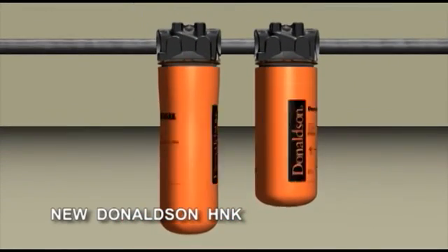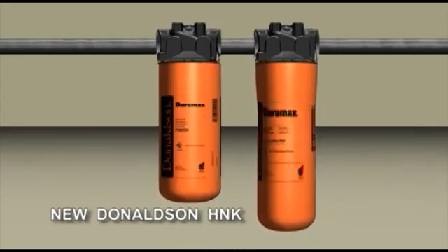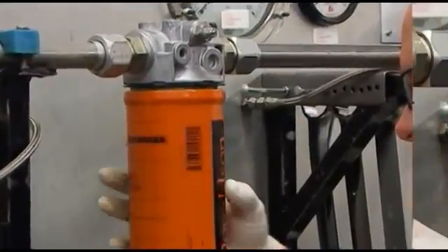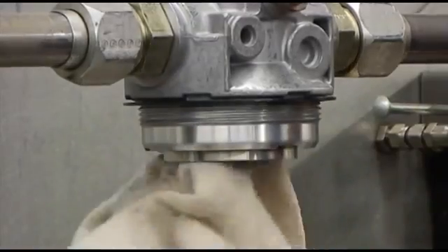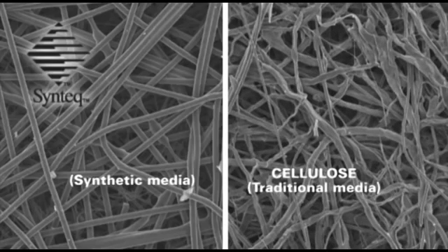This new Duramax filter allows you to choose between a spin-on or bowl cartridge style filter without changing heads. The new filter interface makes service easier and provides reliable sealing without having to torque to specification. Its improved performance is a necessity in some applications for meeting ever-increasing system cleanliness requirements. Although cellulose media will suit some applications, others may require Synteq synthetic media in medium-pressure applications. For the same media area, the Syntex media gives a lower pressure drop than the cellulose media due to thinner fibers.